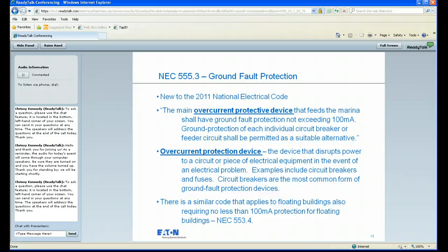Now, to give you a definition of what an overcurrent protection device is: basically the kill switch or the kill mechanism if there are any issues within the electrical circuit that will cut off power to that circuit. Circuit breakers and fuses are common examples of these overcurrent protective devices. Circuit breakers are by far the most common form using the ground fault protection. Somewhere within your electrical system, this new code requires you to have 100 milliamps of protection, meaning that anything that exceeds that 100 milliamps is going to turn off everything that is attached to that electrical protective device.